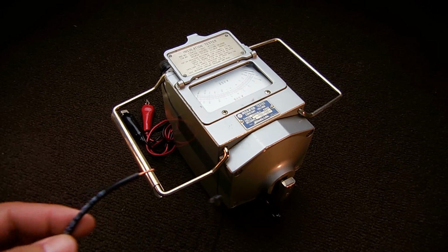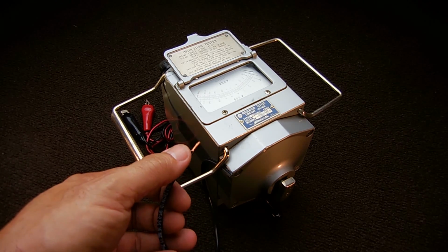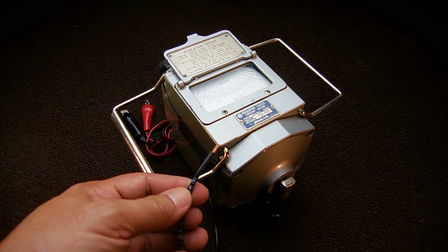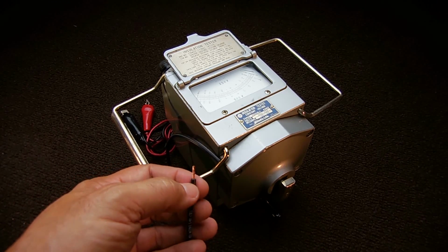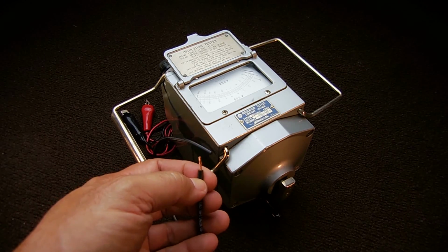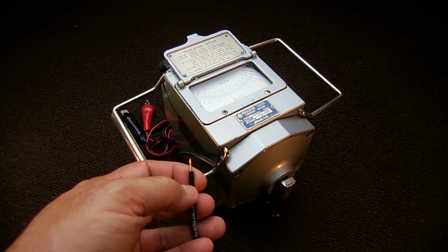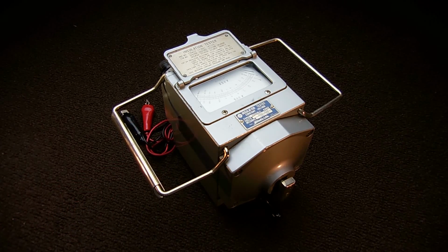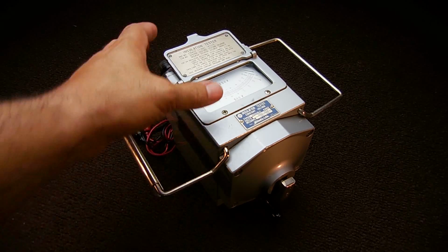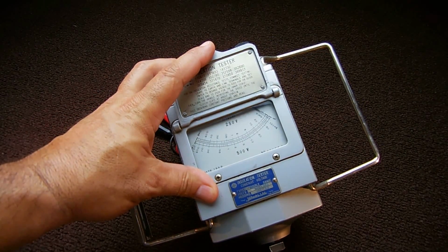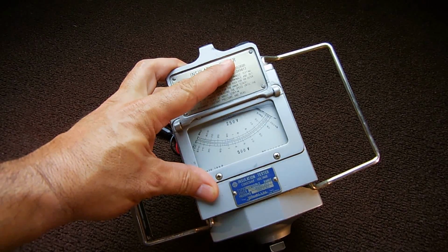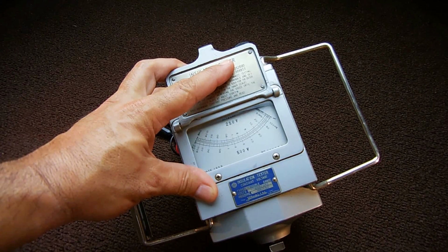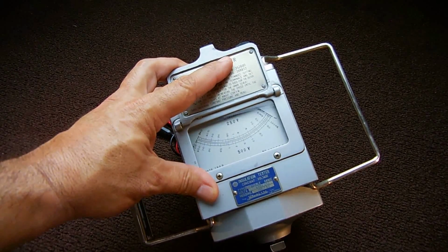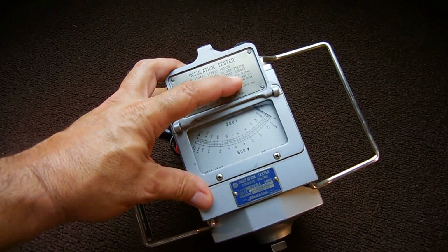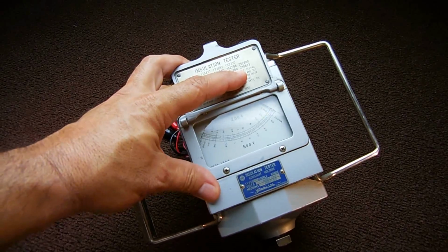The higher the voltage on a conductor, the more current you're going to have leaking through the insulation. It is normal to have a very slight amount of current passing through the insulation at high voltage. You just don't want a lot of current, because if you do, circuit breakers will trip. The reading that you're going to get on a meter like this will be affected by humidity. Low humidity will lead to higher resistance readings, and higher humidity leads to lower resistance readings. Temperature also affects the readings when using a Megger. Let me connect up a wire and show you how to check the insulation on a wire.